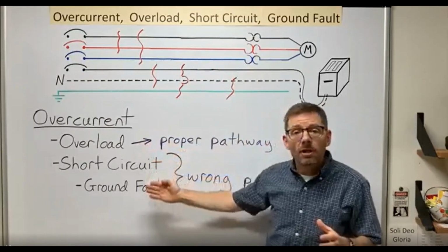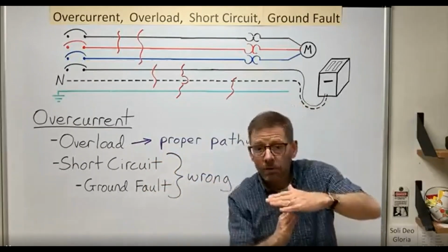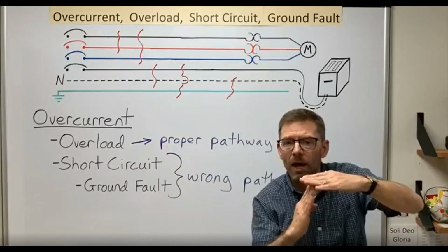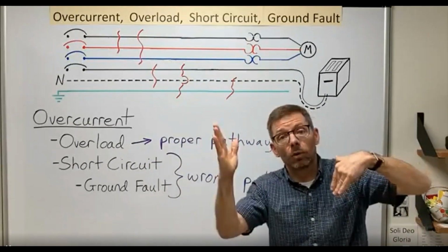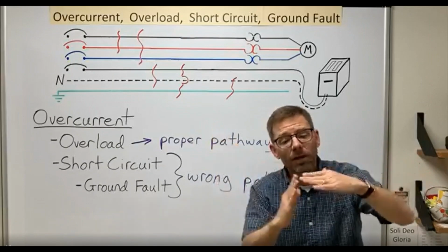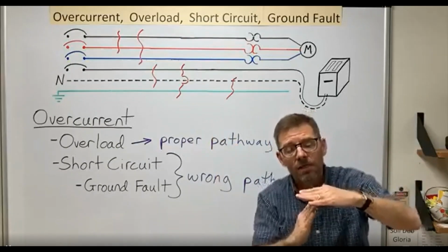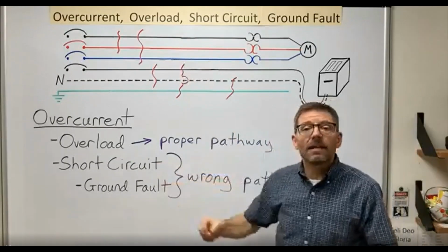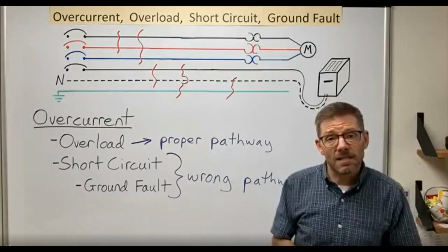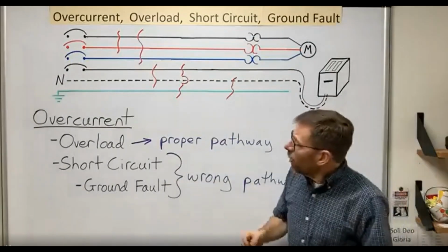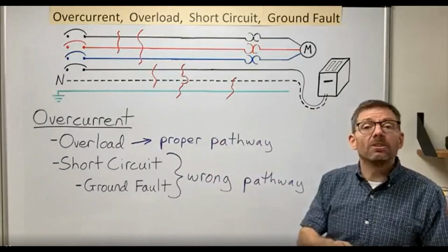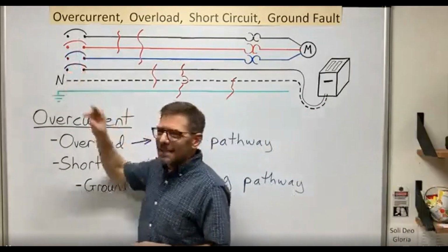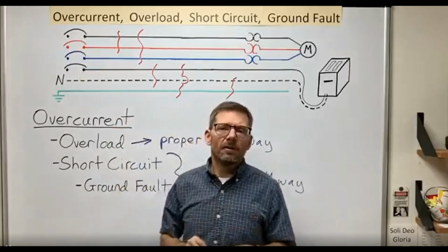So these pieces of equipment are designed to distinguish between overloads and short circuits. For some of them, generally overloads, they'll allow a little extra current for a little while and then open the circuit before things get too hot. But for others, generally short circuits, they'll open right away because the current can be so high that it can do damage almost instantaneously.